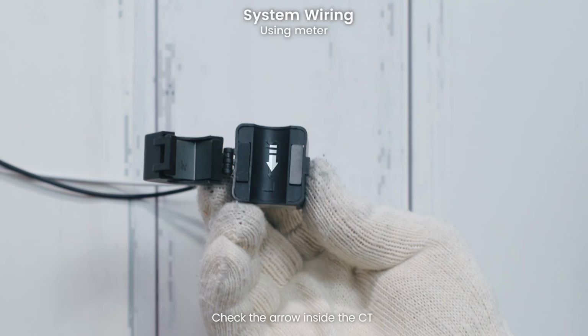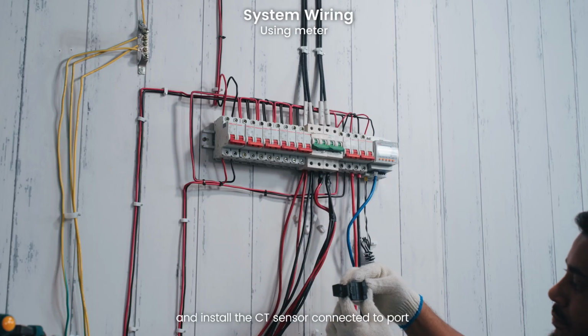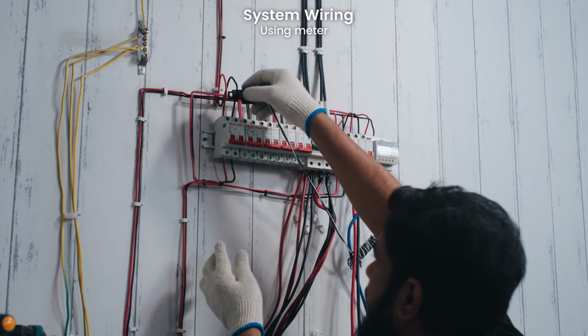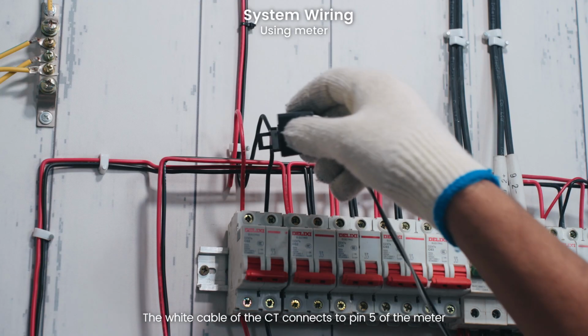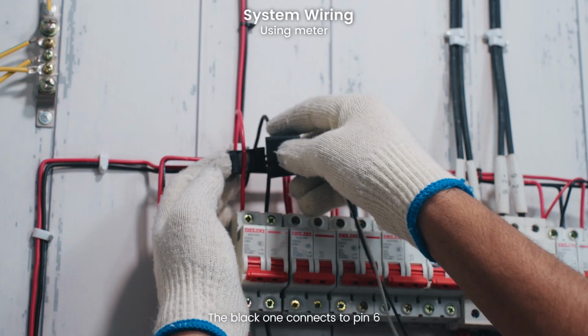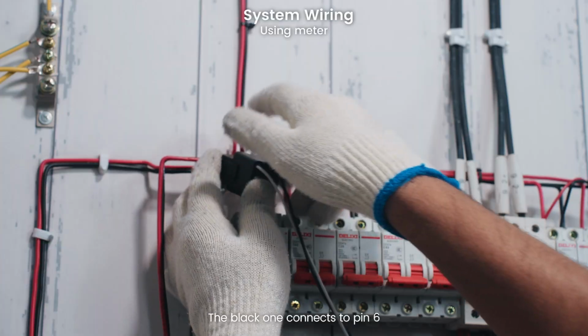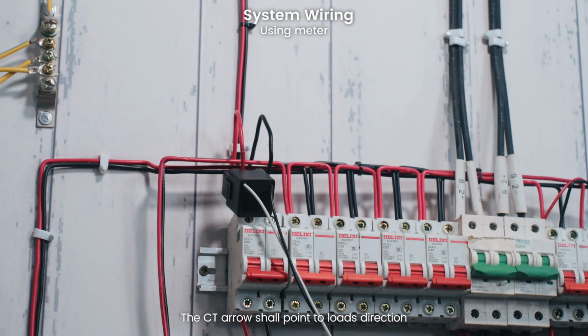Check the arrow inside the CT and install the CT sensor connected to port. The white cable of the CT connects to pin 5 of the meter. The black one connects to pin 6. The CT arrow shall point to the load's direction.